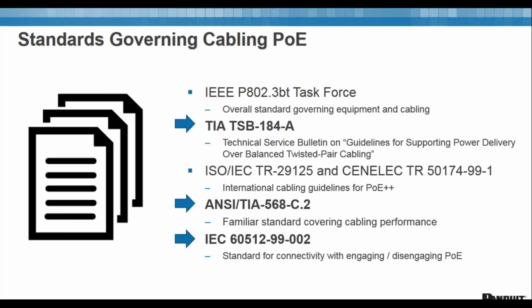So there's TSB-184-A. It's a TSB on guidelines for supporting power delivery over balanced twisted-pair cabling. It discusses a lot of heat rise. And then there's also the ANSI/TIA-568-C.2 standard, which many people should be familiar with. That's the standard that really gives performance requirements for, say, Cat 5e, 6, and 6A. There's also an IEC standard on connectivity with engaging and disengaging PoE. ISO/IEC also have information on PoE, but for today's call, I will not be discussing those details. But they are similar to what we've seen in the U.S.